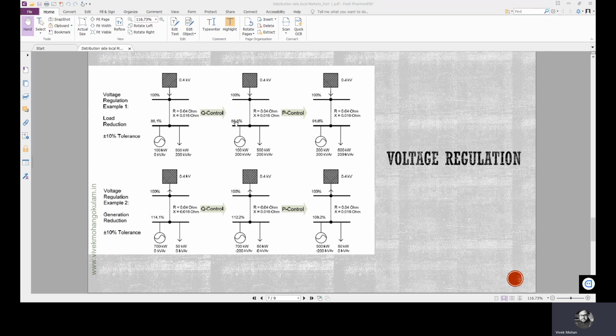Now, in addition to the local reactive power compensation, we are going for active power control also. So for active power control, the local generation has been increased from 100 kilowatts to 200 kilowatts. Now you can see here the voltage profile has further improved and it has become 91.8%, which is in between 90 and 100% and within the 10% tolerance limit.